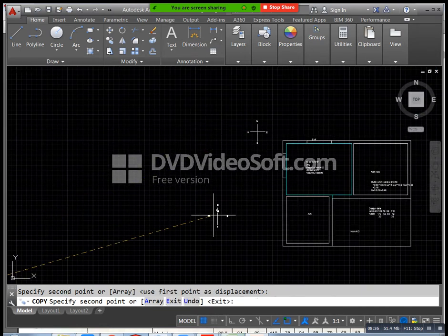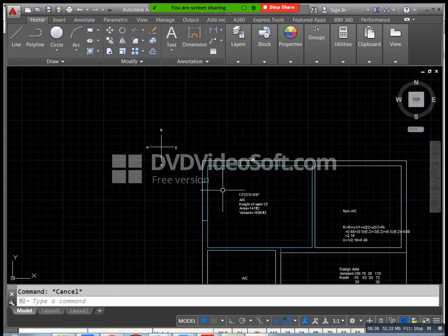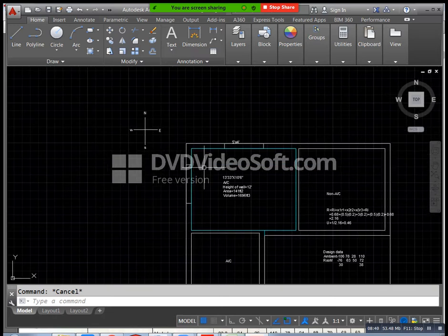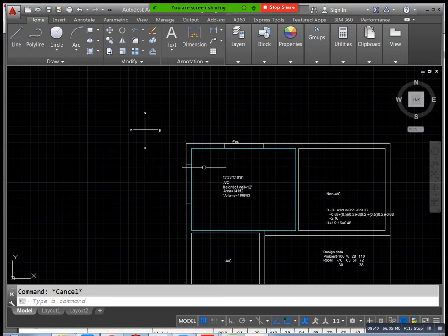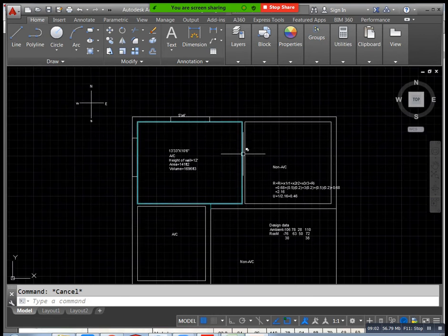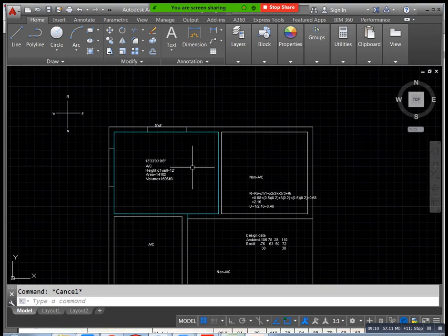Here you can remember only one point. When we are considering a wall, it means directly exposed to the sun. That condition you will consider as a wall. In case you have the inner portion, this inner portion you consider as a partition. We consider it a partition when this is an AC room and this is a non-AC room. In that condition we have temperature differences here and here, so heat automatically transfers from this position to this position, right? That's why we consider this portion as a partition.